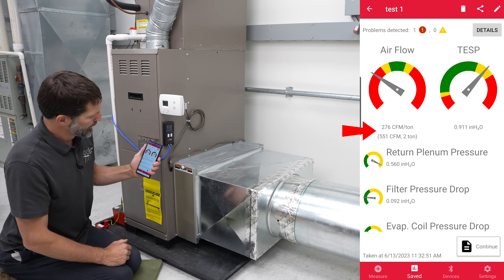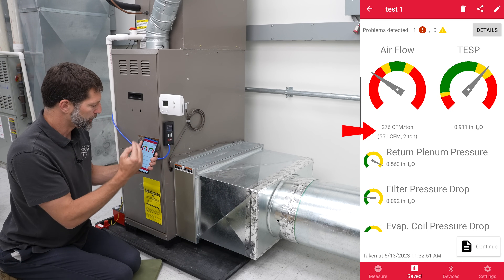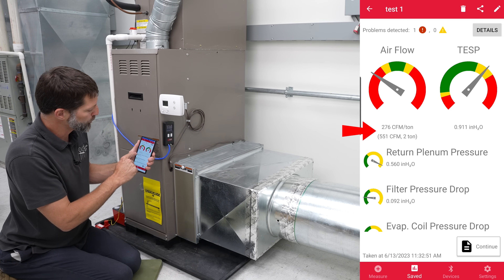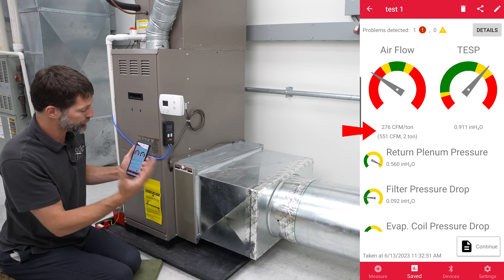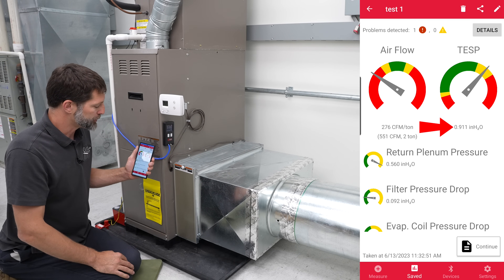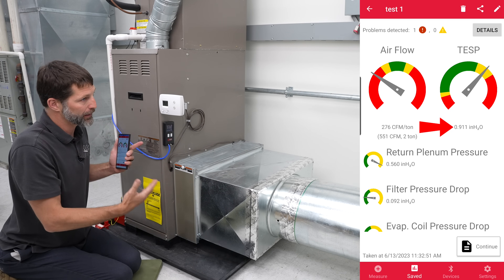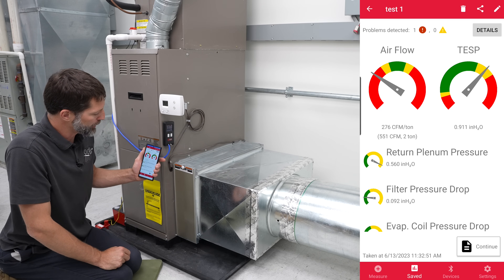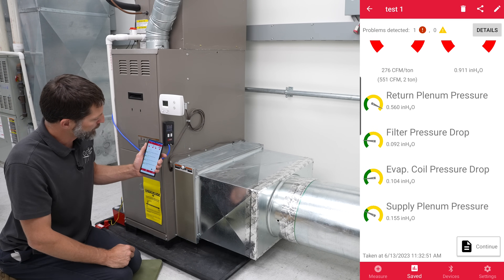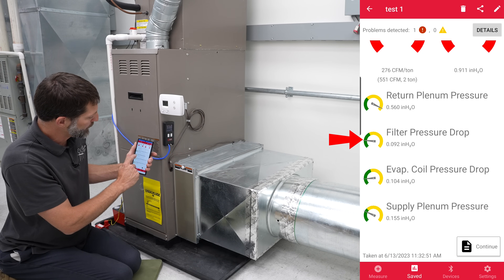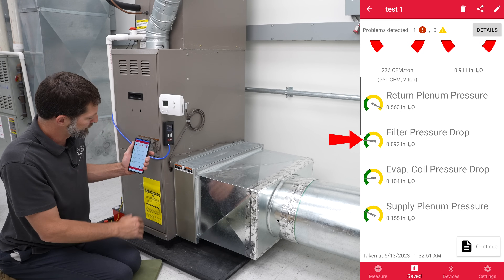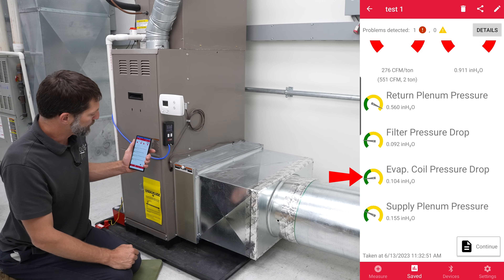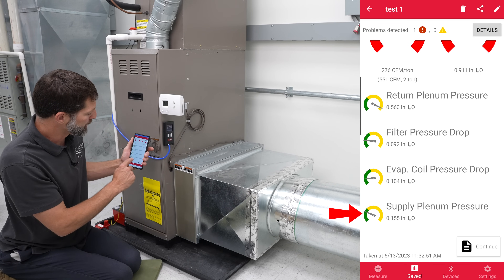It's telling us that we have 276 CFM per ton — much lower than 400 CFM per ton. We have 551 CFM for a two-ton system, so that's extremely low. It's saying our total external static pressure is 0.911 inch water column, which is very high. A lot of furnaces are only rated to blow at high capacity up to 0.5 inch water column. Looking at the breakdown: return plenum pressure is 0.56; filter pressure drop is only 0.092, so less than 0.1 — that's not bad; evaporator coil pressure drop is only 0.1, which is really good; and supply plenum pressure is 0.15, which is pretty decent.